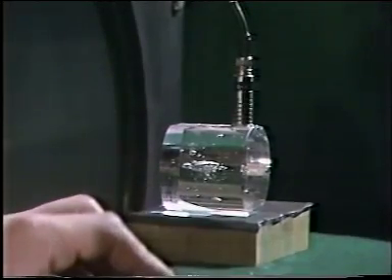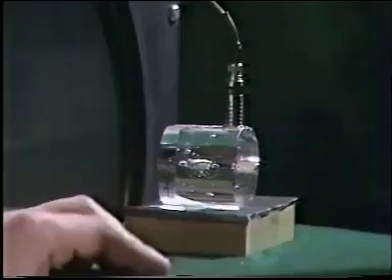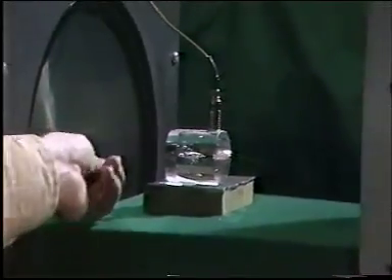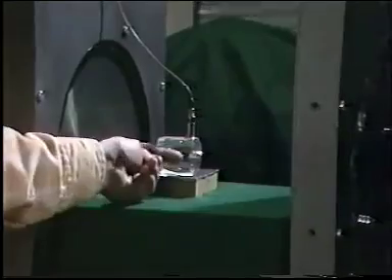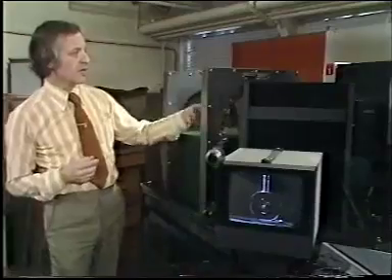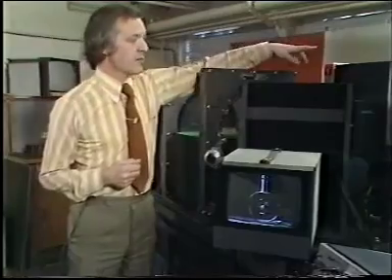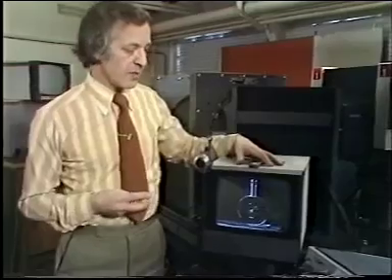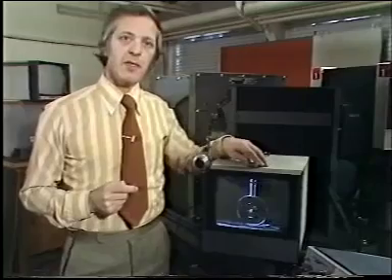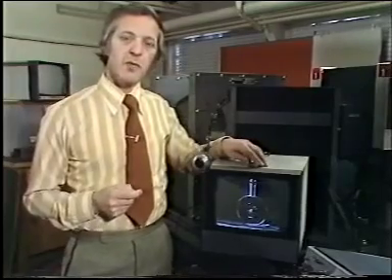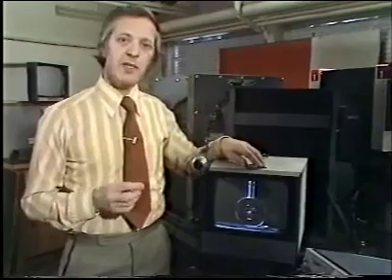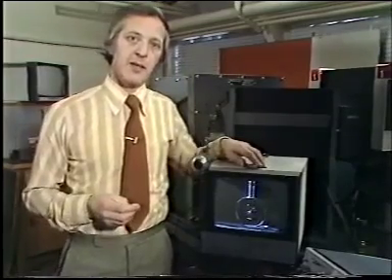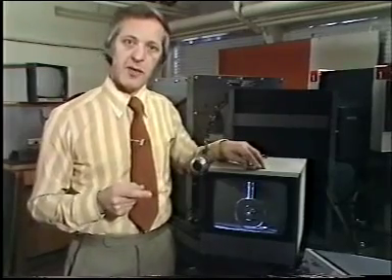Now, we're visualizing the waves by a technique known as photoelasticity. We send light through a polarizer here, through the glass block, through a second polarizer. The light bounces off a mirror, goes into a TV camera, and the picture appears on this monitor. I've still got it switched off at the moment. Photoelasticity enables us to see static stresses, but of course ultrasonic waves are dynamic stresses, and what's more, the waves move. So to make them appear stationary, we use a stroboscopic technique. What we do is we flash the light at the same rate as we send the ultrasonic pulses out. Let's switch on.